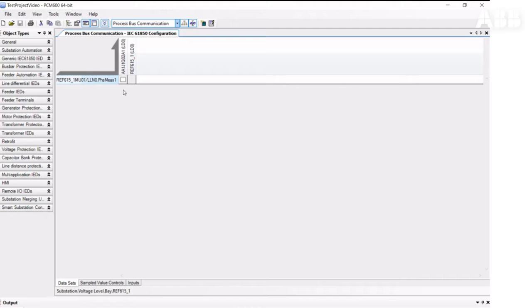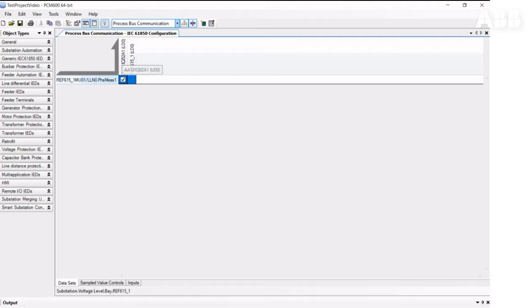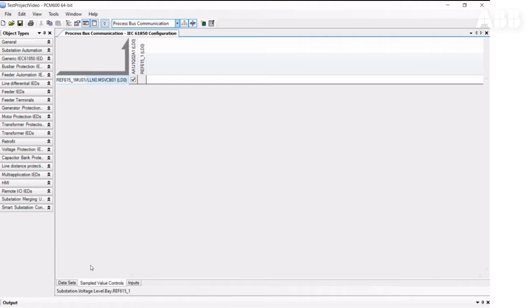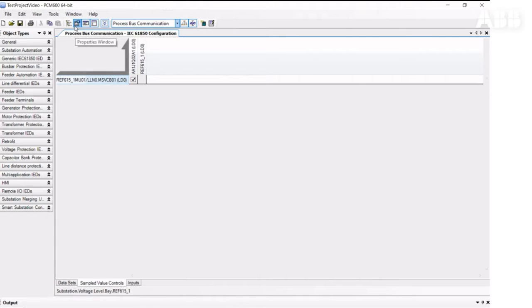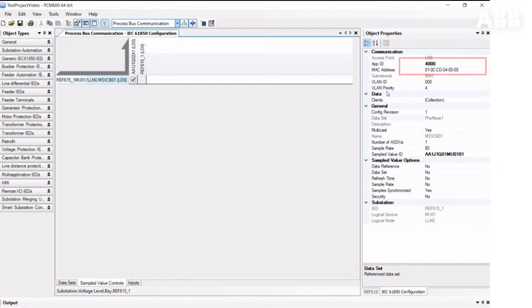Let's check what kinds of parameters we can see in the sample values control. When you connect the dataset to the receiver, the tool automatically creates a sampled value control element. According to the IEC 61850-9-2 LE specification, we need to leave the APP ID value at 4000.